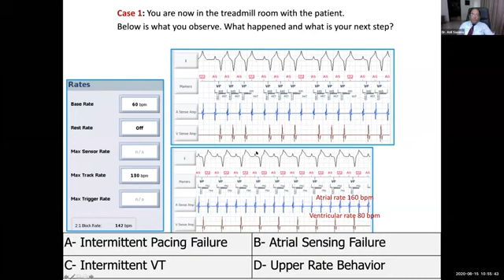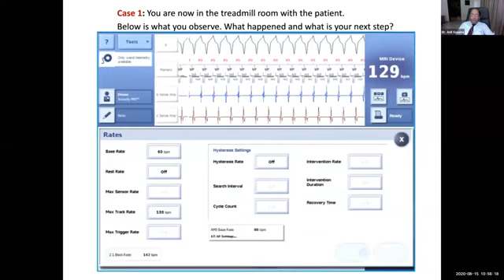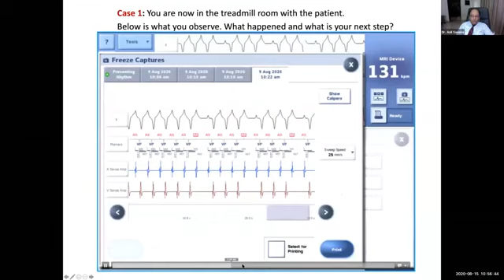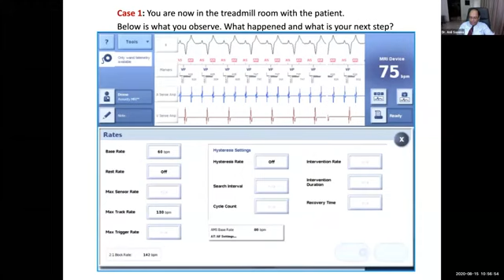And as the patient exercises and the heart rate increases up to 120, we can see that there is one-to-one conduction. But as the heart rate goes beyond 130, the patient is expected not to continue to increase the heart rate, but the pacemaker develops a kind of Wenckebach pattern. So we call it pseudo Wenckebach because it is happening by the pacemaker, and the heart rate remains fixed at 130. So the pacemaker tries not to increase the heart rate beyond what we have set up as the upper tracking rate. So there will be progressive prolongation of the AV delay till the P wave will be dropped. And as the heart rate increases further, a rate will come when the patient will develop 2:1 AV block. So that is called top rate, as has already been explained. So this is the problem that the patient is facing.